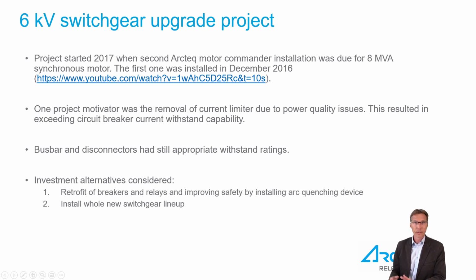Current limiters do their job, limiting the fault currents, but side effects quite often involve power quality issues. So was the case here as well. Once the reactor was removed from the system, the withstand capacity of the circuit breakers was exceeded. Luckily here, the busbar and disconnectors still had appropriate withstand ratings. This in turn gave two investment alternatives. One, retrofitting breakers and relays and improving the safety by installing the arc quenching device. Or another alternative considered by the customer was installing a totally new lineup of switchgear.